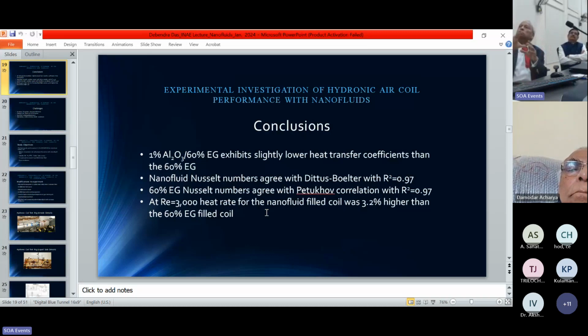From this initial set of experiments it opened our eyes: 1% aluminum oxide exhibits slightly lower heat transfer coefficient than 60% EG. The only plus is a slightly higher heat transfer coefficient. Nanofluid Nusselt number agrees with the Dittus-Boelter equation, so we'll always use that equation to check further experimental values. 60% EG, which is pure, agrees very well with the Petukhov correlation, so by and large the experimental setup replicates what the old theory predicted. At 3000 Reynolds number, we found the heat rate of the nanofluid coil was 3.2% higher than the 60% EG fluid coil. These results are by no means very promising, and they disappointed us.